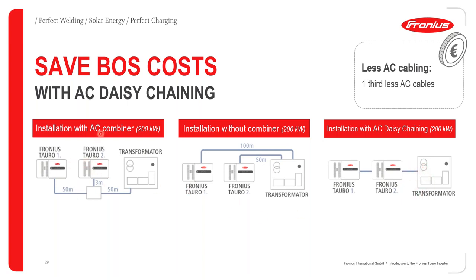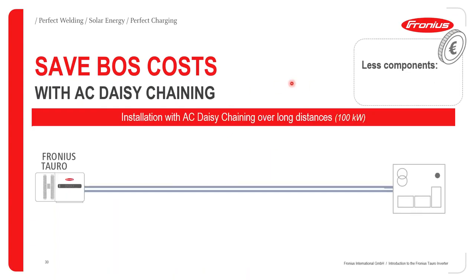Also, in this particular case, with the AC combiner we are going to require, in addition to the AC combiner box, one AC disconnector here. And therefore, we can see the cost with an AC combiner will definitely be slightly higher, because we need the AC combiner as well as the AC disconnector. In the case without it, we are going to incur the cost of 2 AC disconnectors in addition to much longer cable distances. The longer we cover with the cables, the more likely you are to have cable losses in your system.